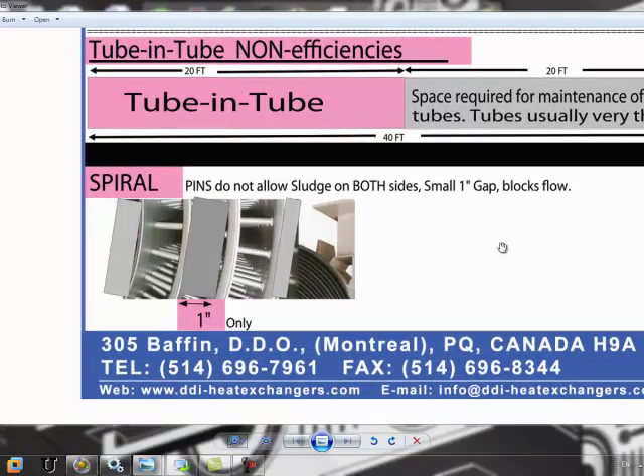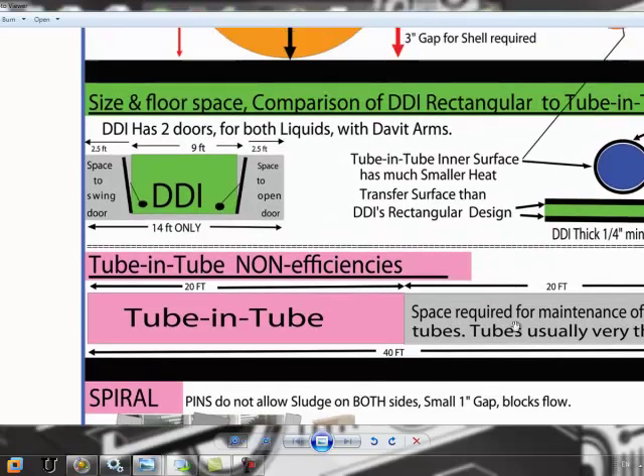Compared to spiral technology, most consulting engineers avoid it because even one to two percent digested sludge causes problems — let alone four, five, or six percent raw sludge. The spiral cannot have more than a one to one-and-a-half inch gap, so only digested sludge can pass through it. The other channel can only carry water because of the pins that maintain spacing. This makes it impossible for spiral technology to handle sludge-to-sludge heat recovery or high-percent solids applications.